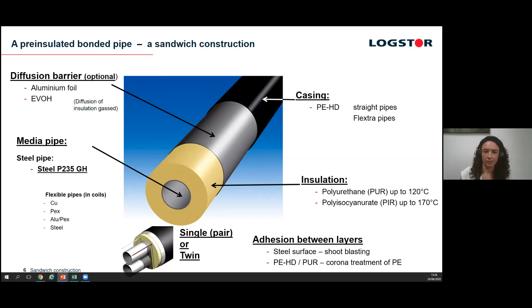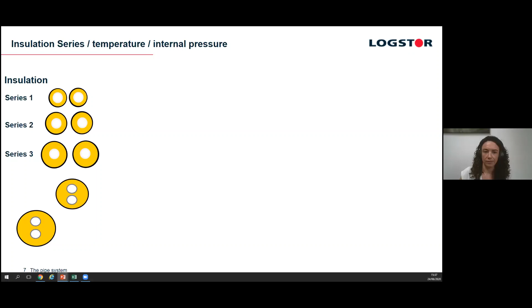We can get them as a pair of single pipes for flow and return, or if you want, you can have them both in one single PE casing, which is your twin pipe. The next consideration in terms of design is what series, or insulation thickness, you want. I'll talk about this in more detail, but insulation is really about how much heat you will lose over time, and that's the key element when looking at system design, balancing the cost of the capex against the operation and maintenance costs, and obviously the fuel source you're going to use over time. But you'll be looking then at your pipe.